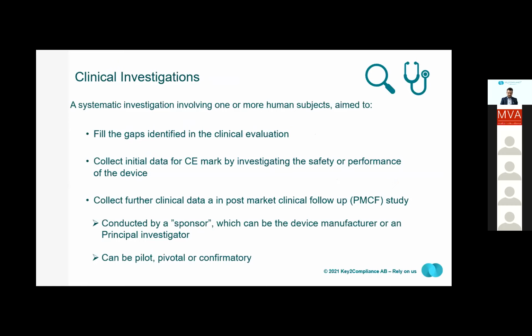So, clinical investigation. The MDR defines a clinical investigation as any systematic investigation involving one or more human subjects undertaken to assess the safety or performance of a device. The aim of a clinical investigation is to fill the gaps that are identified in the clinical evaluation. You can collect initial data for a CE mark by investigating the safety and/or performance of the device, or you could collect further clinical data in a post-market clinical follow-up, a PMCF study.